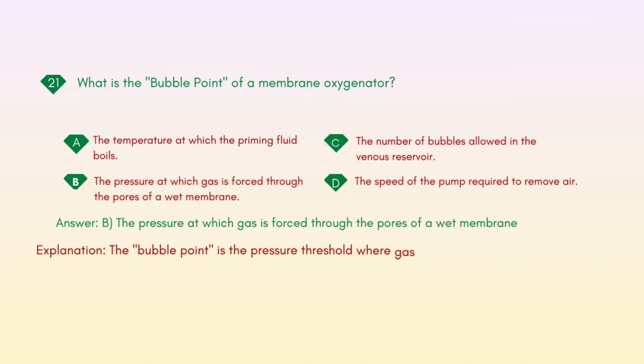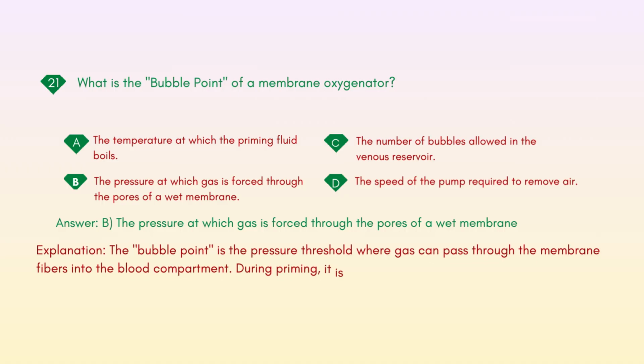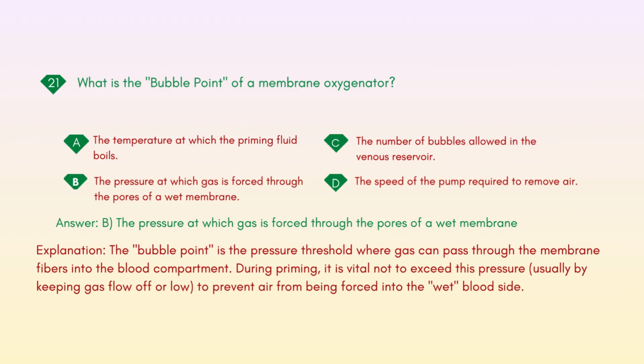Explanation: the bubble point is the pressure threshold where gas can pass through the membrane fibers into the blood compartment. During priming, it is vital not to exceed this pressure, usually by keeping gas flow off or low, to prevent air from being forced into the wet blood side.